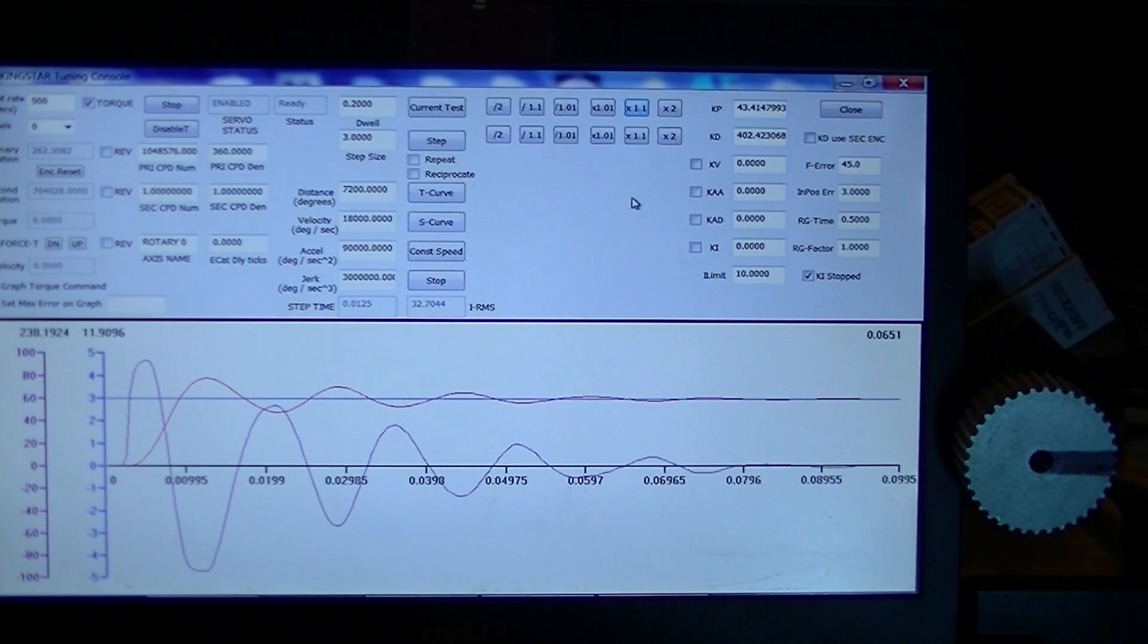At this point, I think it's safe to go out and run a traditional trapezoidal move. Here we have commands set up: 72 degrees, 7,200 degrees. That is 20 revolutions. 18,000 degrees per second, that's about 3,000 RPM. The acceleration is chosen to get up to speed in 200 milliseconds.